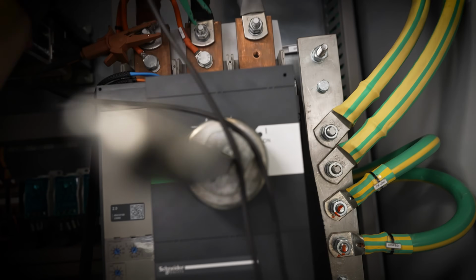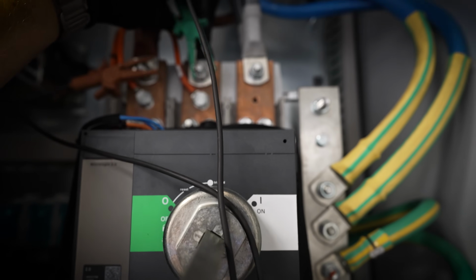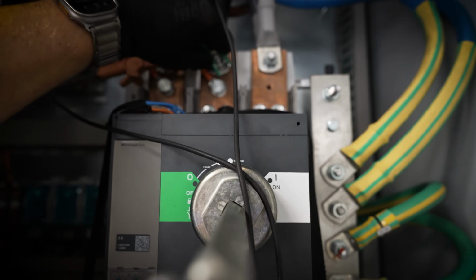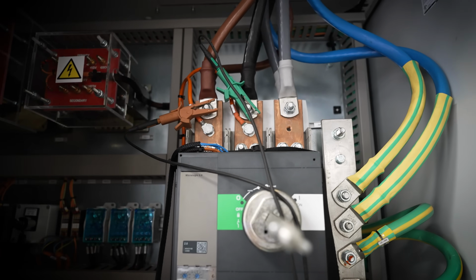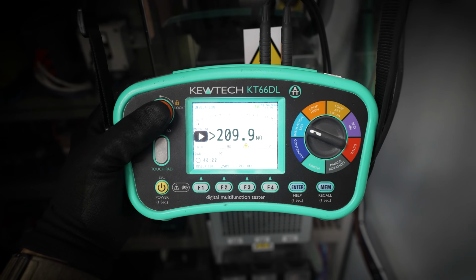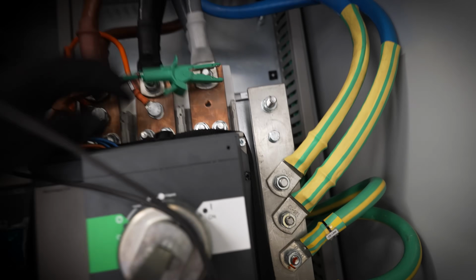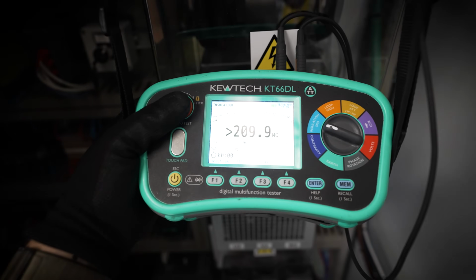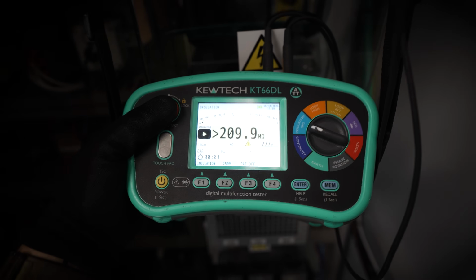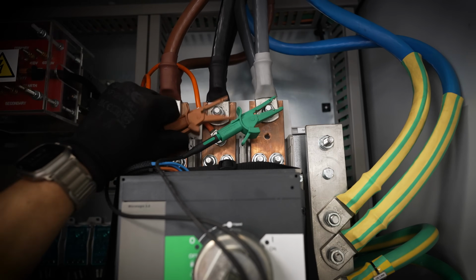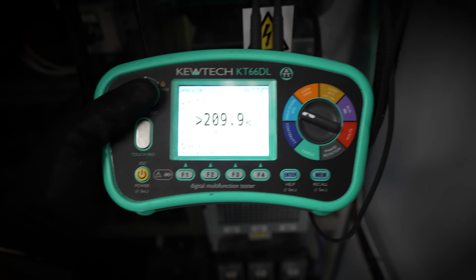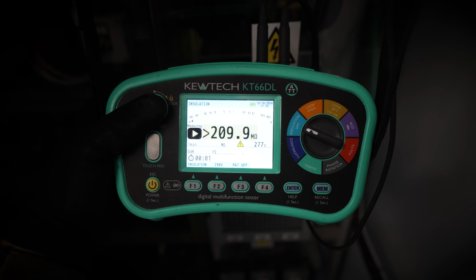And now we can go between the phases. So we're going to go between L1 and L2. Greater than 209.9. L1 and L3, greater than 209.9. And then between L2 and L3, greater than 209.9. So that is our dead test done. That has also confirmed polarity.